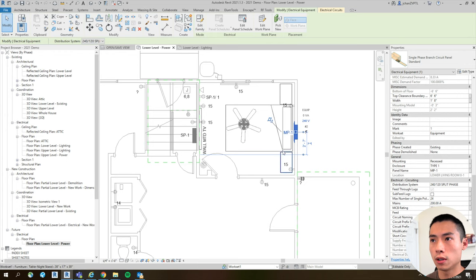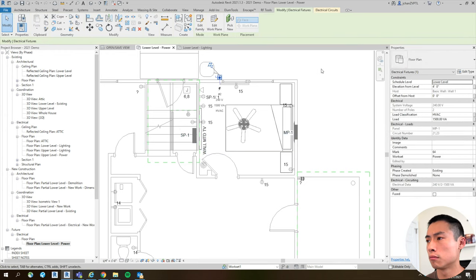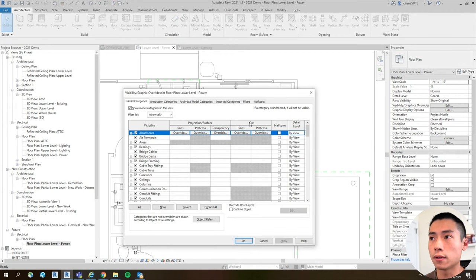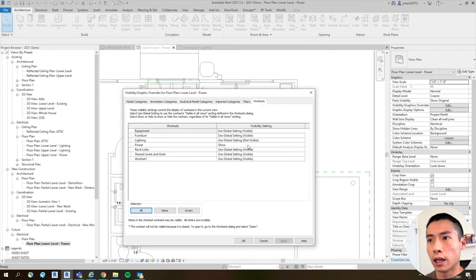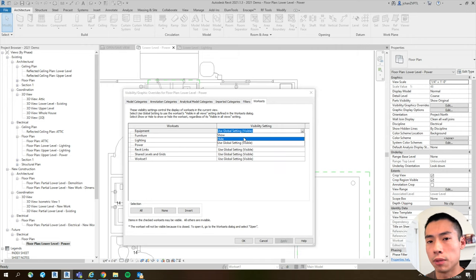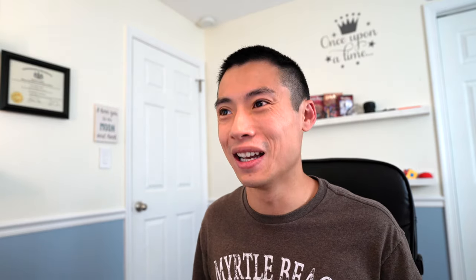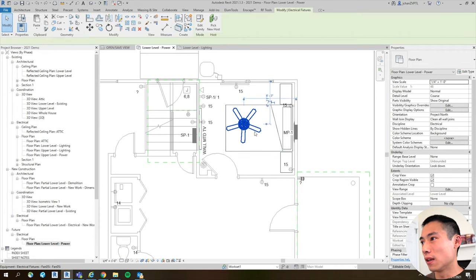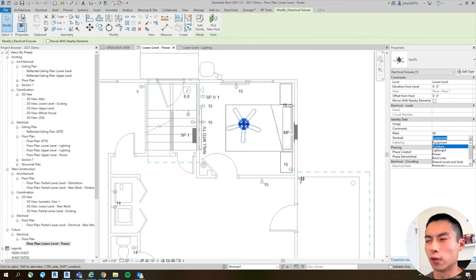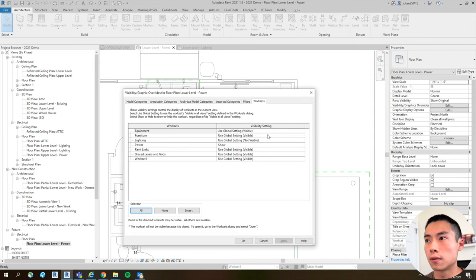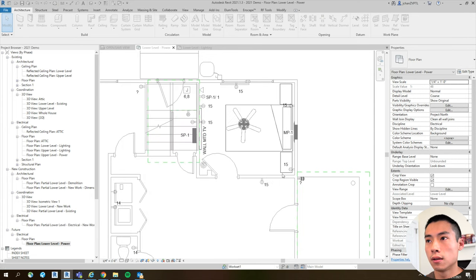There's Equipment and the other equipment — we'll leave that. Then under your Visibility Settings, go to Work Sets on the far right. Here we have Power showing, Furniture showing, and Equipment we can set to hidden. When I hit OK, it takes the panels away, but it also took my ceiling fan — so my ceiling fan wasn't on the right work set. I'll switch the ceiling fan to Furniture, hit Apply. Now if I turn off the Equipment work set and hit Hide, OK — there we go.